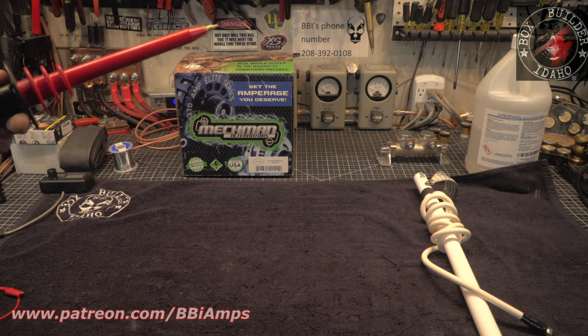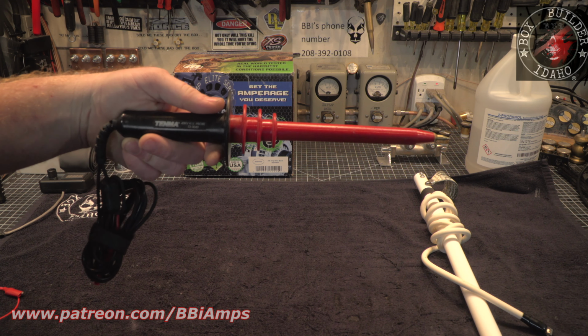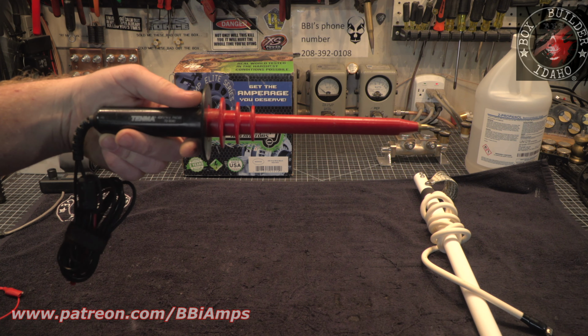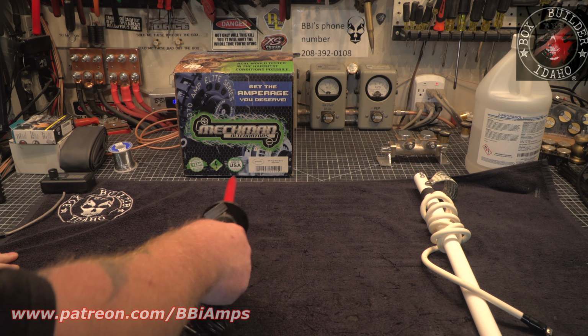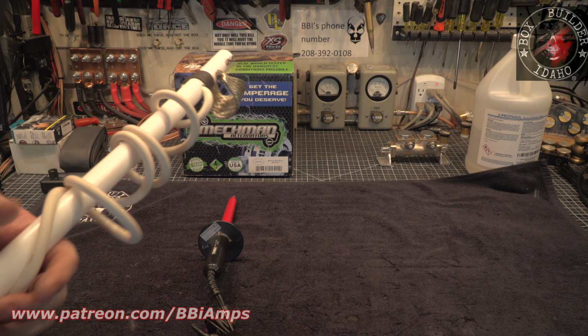This is a Tenma, a 40 kV, 100 to 1 high voltage reduction probe. The sheer length of the surface area distance between here and here is what keeps me alive when you see me stick one of these inside an amp. I verify with a high volt probe, then I ground and I neutralize.